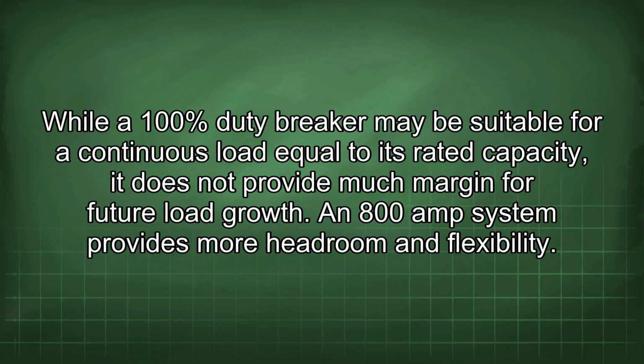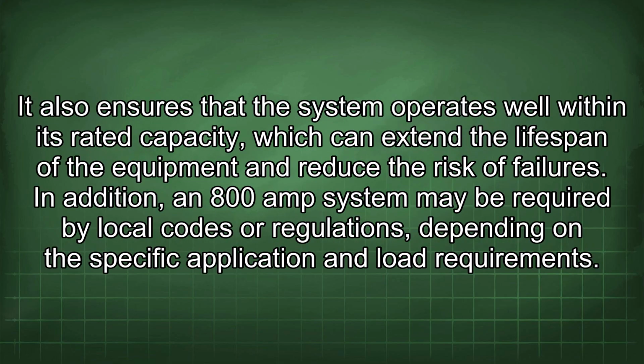While a 100% duty breaker may be suitable for a continuous load equal to its rated capacity, it does not provide much margin for future load growth. An 800 amp system provides more headroom and flexibility. It also ensures that the system operates well within its rated capacity, which can extend the lifespan of the equipment and reduce the risk of failures. In addition, an 800 amp system may be required by local codes or regulations, depending on the specific application and load requirements.